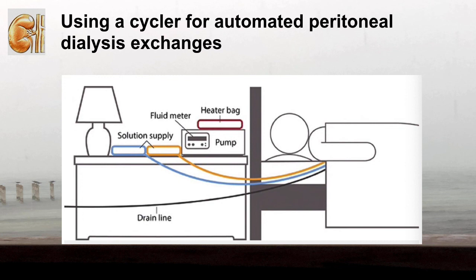At the times you set, the cycler releases a clamp and allows used solution to drain out of your belly into the drain line, warms the fresh dialysis solution before it enters your body, and releases a clamp to allow body temperature solution to flow into your belly. A fluid meter in the cycler measures and records how much solution the cycler removes. Some cyclers compare the amount that was put in with the amount that drains out. This feature lets your doctor know if the treatment is removing enough fluid from your body. Some cyclers allow you to use a long drain line that drains directly into your toilet or bathtub. Others have a disposal container.